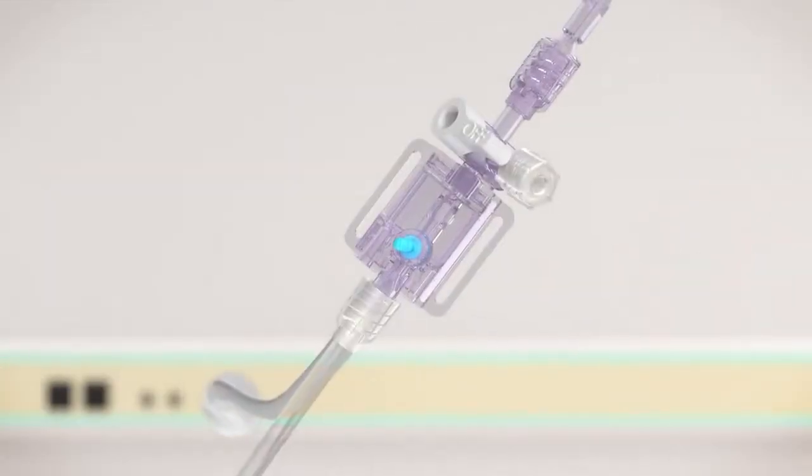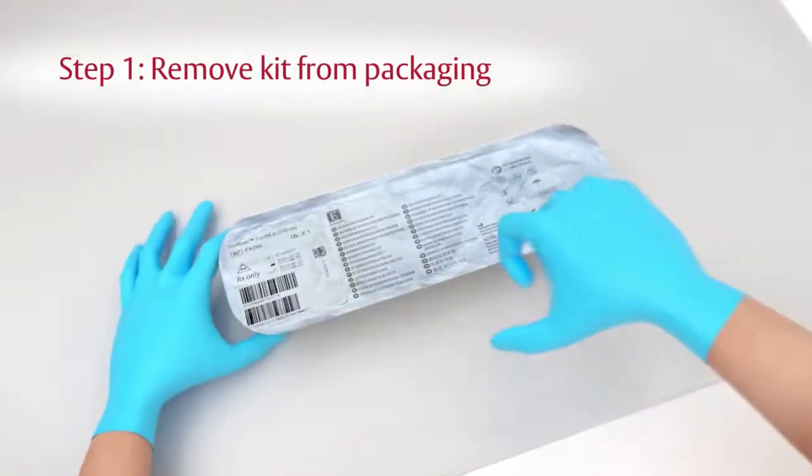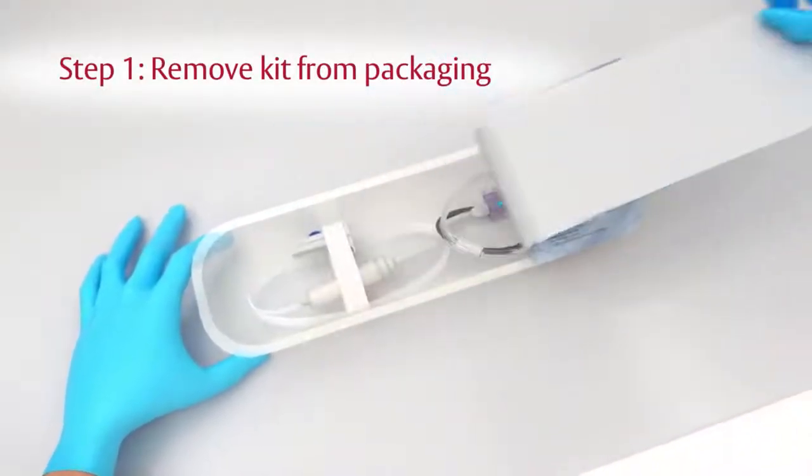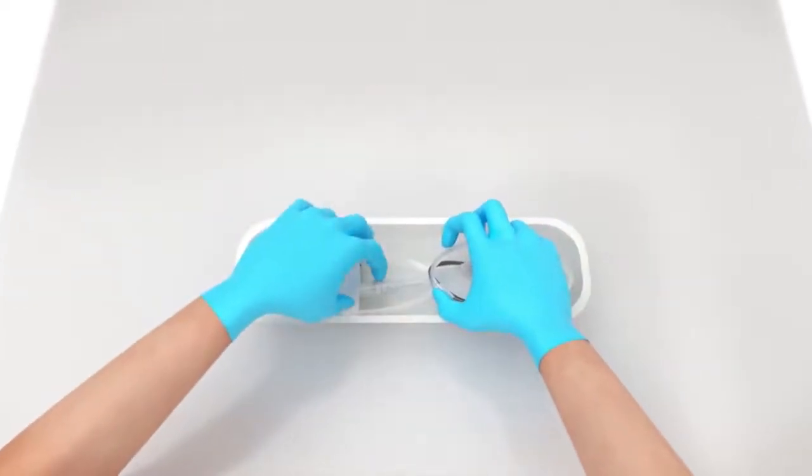Prepare the TruWave transducer using the following five steps. Step 1: Using aseptic technique, remove the transducer kit from the sterile packaging and ensure all connections are secure.